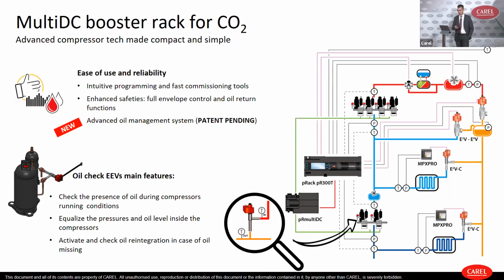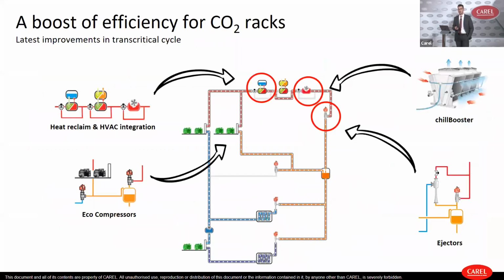Let's have an overview of other improvements that we can make for a standard booster system with reciprocating technology. So how can we improve the efficiency of these systems? Of course, on the left, you can see that there is the heat reclaim possibility, in order to recover some waste heat before the gas cooler for floor heating or domestic hot water. There are the eco compressors, I mean the parallel compression line that you can activate in case of high external temperature in order to manage the high mass flow of flash gas that is coming from the receiver.